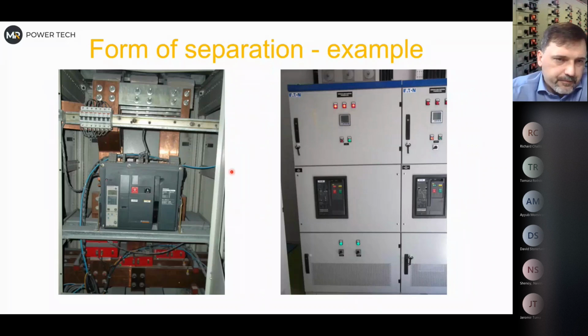So if you travel, and this was one door just to open, and you see this, you know, okay, there is no form of separation. It's like form 1 or 0. You can grab everything here. You can touch everything here. Generally it's bad. On the other hand, that was the same place, you have this, and I didn't actually have to open it to collect the photo. That's why I don't have a photo inside, because the front of the breaker was accessible, and everything else was closed. I didn't have to open it.